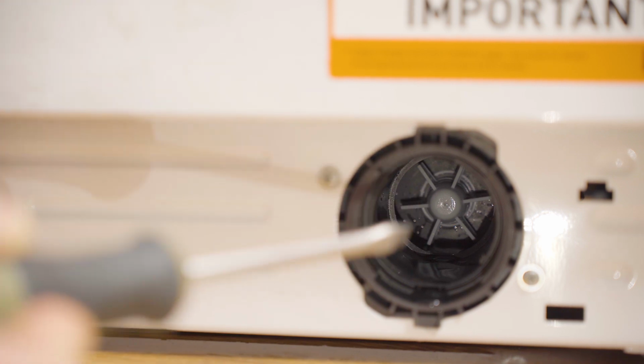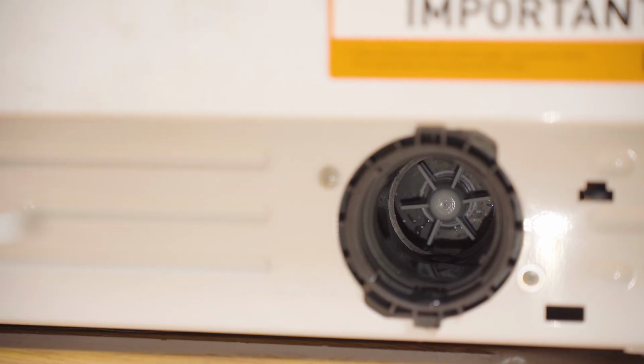You can use a screwdriver here to rotate the impeller. If it's okay, you should feel a bit of resistance as you move it. However, if there's no resistance and the impeller moves freely, that signals a fault. In this case, the pump itself would need to be replaced.